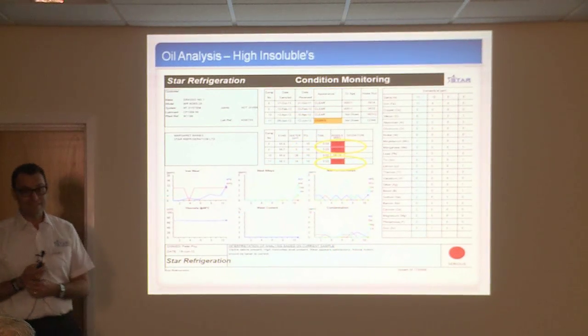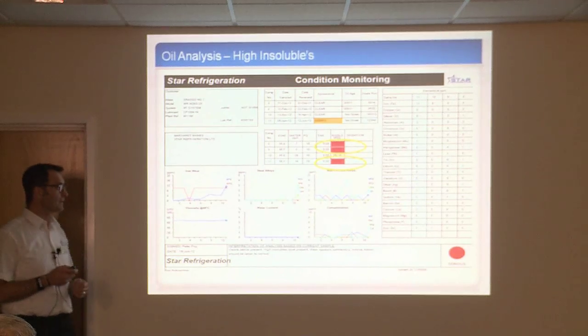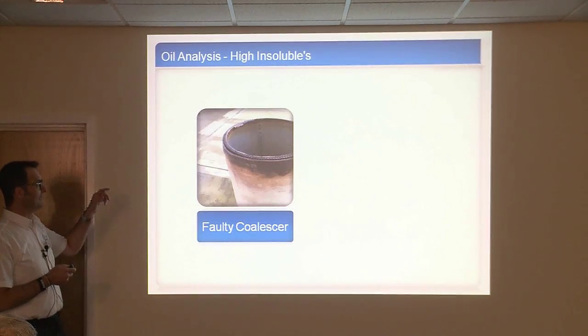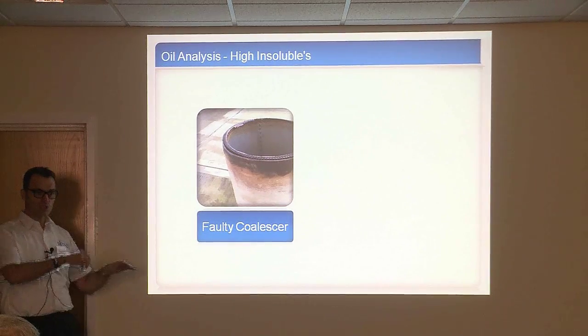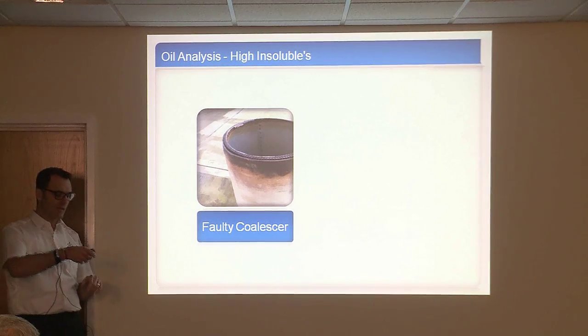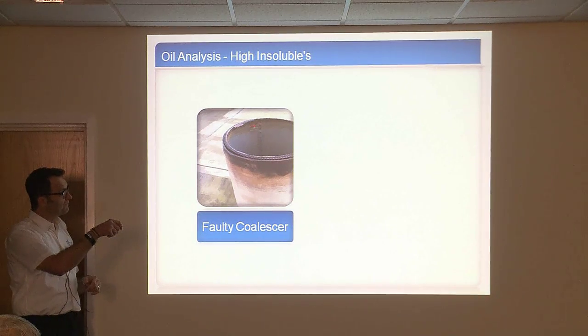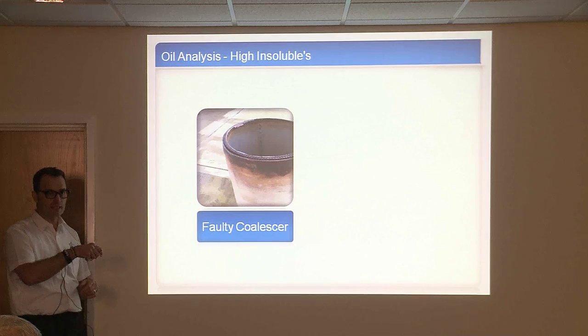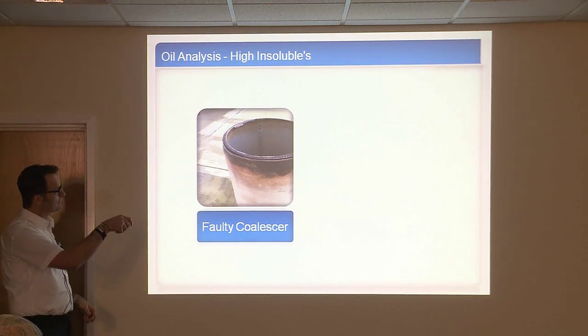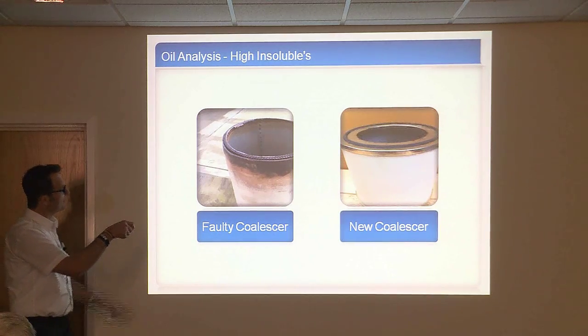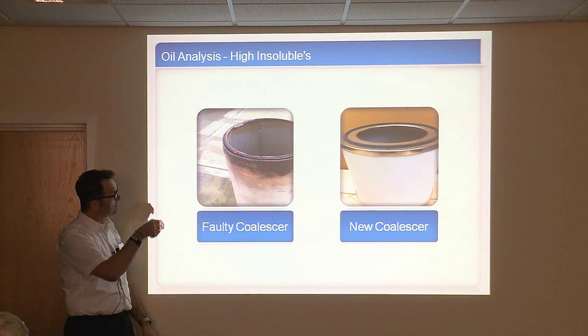And what we found, and it took us a wee bit of time, is that on the third stage of oil separation, we have these coalescer filter arrangements here. We compared that with a new one and found that this bonding had all melted.